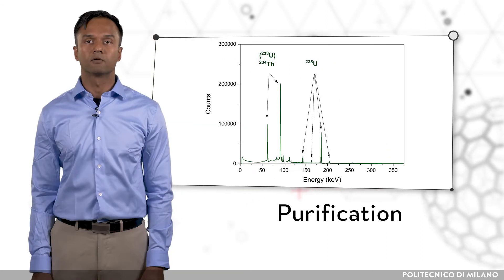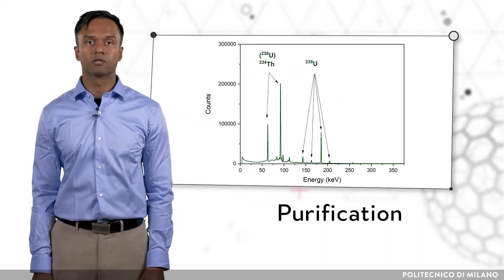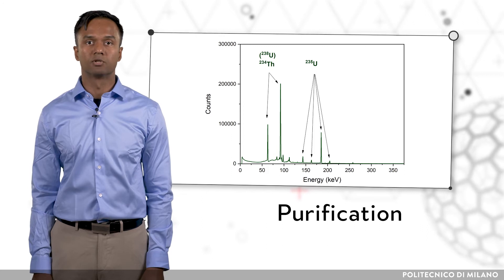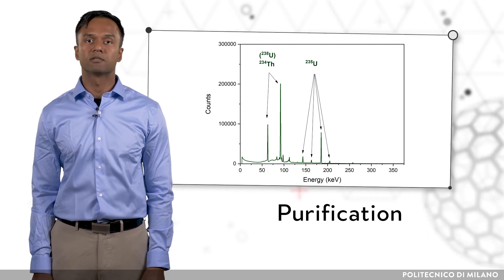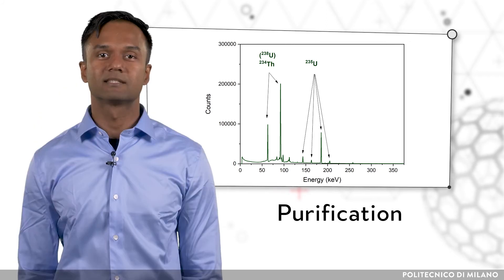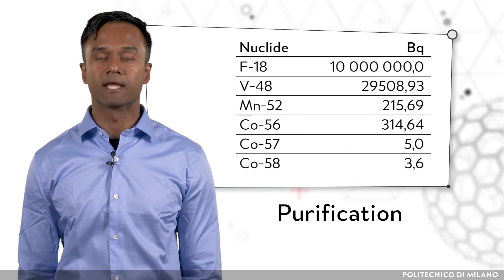The purity of the radioisotope, both radioisotopic and radionuclidic, can be determined using a gamma spectrometer. Let's see the data for the purity of fluorine-18.